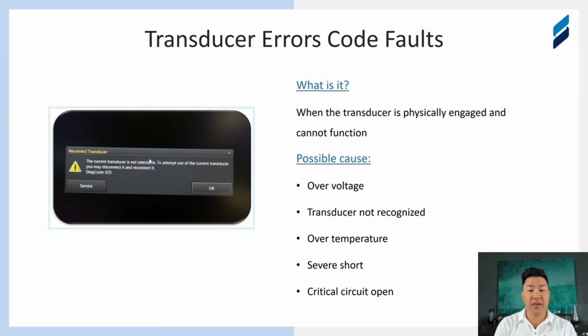And then from an electrical perspective, this could be an over voltage error. It could be transducer not recognized. It could happen during runtime. So, sometimes probes get over temperature and they just throw an error. And a severe short, or some of those critical circuits, they're open when they should be shorted, like maybe a high voltage power line. So the probe just can't turn on. So this is an example of an error that's catastrophic, and the probe needs some sort of repair or service to get that thing functioning again.